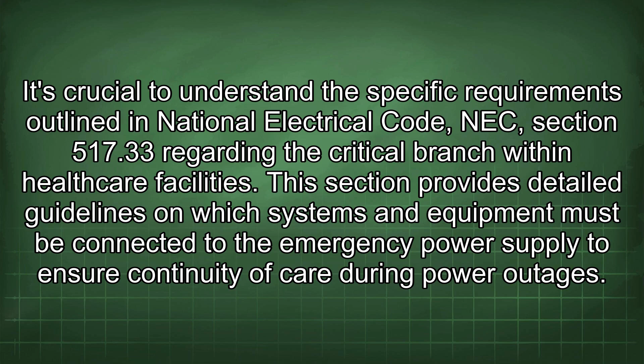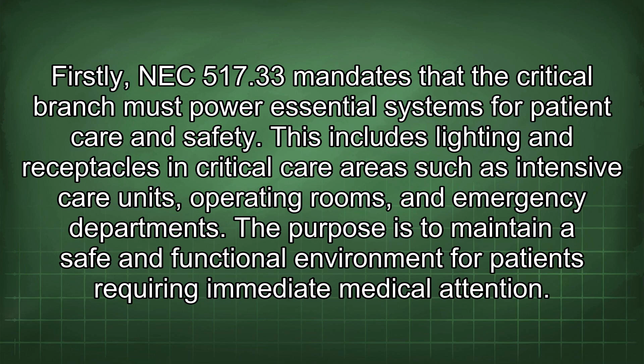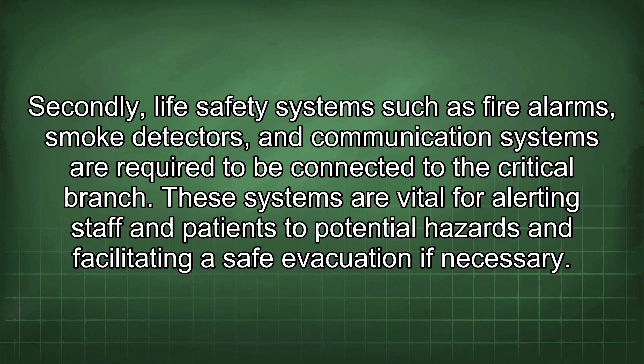This includes lighting and receptacles in critical care areas such as intensive care units, operating rooms, and emergency departments. The purpose is to maintain a safe and functional environment for patients requiring immediate medical attention. Secondly, life safety systems such as fire alarms, smoke detectors, and communication systems are required to be connected to the critical branch. These systems are vital for alerting staff and patients to potential hazards and facilitating a safe evacuation if necessary.